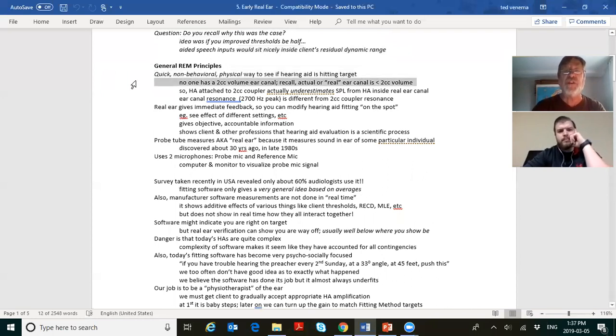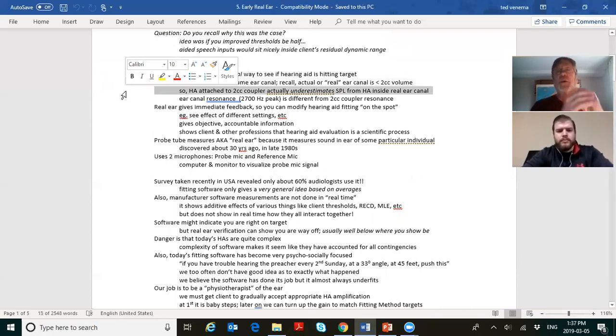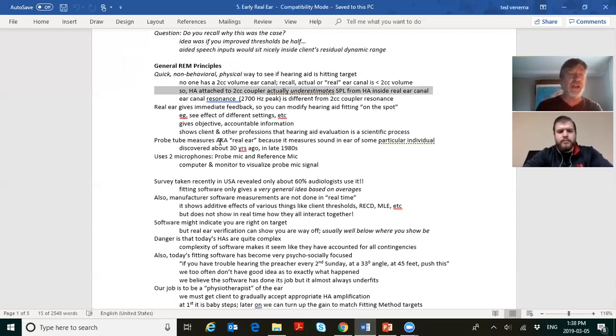No one has a 2 cc volume ear canal. Recall, the actual real ear canal is less than 2 cc's volume. So here's one that a lot of people get wrong on quizzes and tests. 2 cc couplers underestimate the sound pressure level from the hearing aid that actually is taking place in an ear canal. A lot of people get that one wrong, true or false, or I'll say circle 1. Yeah, the 2 cc coupler, circle 1, overestimates, underestimates. And so many people say overestimates, and it's actually wrong, because if you have a larger space, then your SPL goes down. The smaller the space, the higher the SPL.